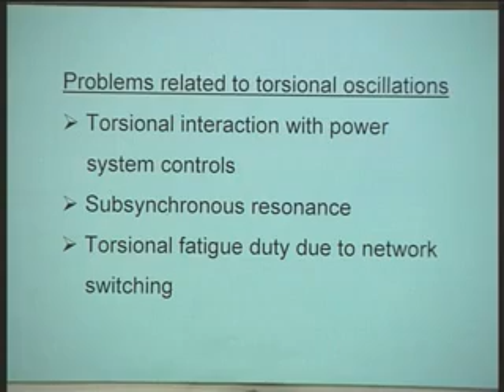excitation controls. Now, we have studied that power system stabilizers are used for damping the system modes of oscillations, that is the power system oscillations in the frequency range of 0.2 to 2 hertz. Here, when we design the power system stabilizer, we ensure that a component of electrical torque produced is in phase with the speed deviation signal, and the parameters of the power system stabilizers are so chosen that we get a component of air gap torque in phase with speed deviation, and this is a pure damping torque.